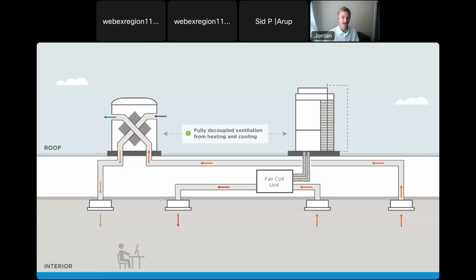units. They do that in a very high efficiency application with a heat recovery or energy recovery ventilator that delivers at least 82% sensible effectiveness. We find that to be extremely important, especially in climate zone 4, so kind of the coastal marine climates, because typically we can drastically simplify a system when we get to this level. We can deliver ventilation directly to the space year round without any supplemental heating or cooling, as long as you follow some kind of proven design strategies. You can do this without duct heaters.